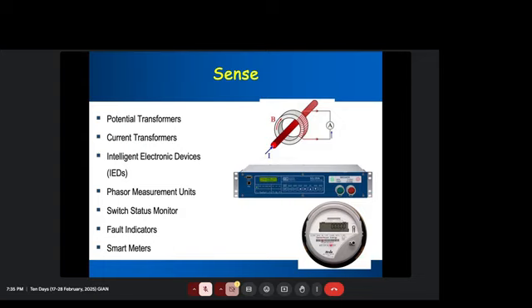You still need something like a CT and PT to tie with the smart meter, so it can take those analog signals and convert them to a value which it can process, which has to be low voltage and low current, right? As soon as you get to digital electronics, you typically have plus or minus 5 volts or plus or minus 10, not more than that. So anytime you're dealing with the power grid, which has very high voltage and high current, you have to bring it down before you connect to any of these IEDs, any of the PMUs, smart meters, and any of those RTACs that we talked about.